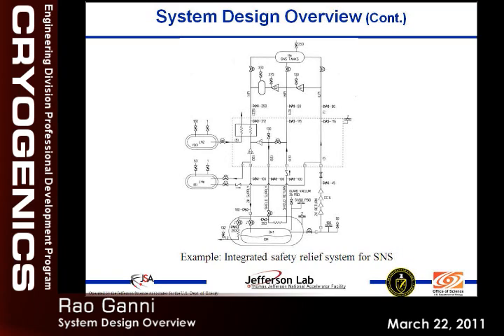So when we designed the SNS, with the industrial standard where we came from, with our background, we lose only like 1/10 of what we lose here in the helium. Not even 1/10, probably 1/20th. They lose half a tube trailer versus we lose 3 a month, every 3 weeks. So there's a substantial difference in helium usage when it is designed with those margins appropriately addressed, when all this is stacked appropriately, and all your utilities will come down with it.